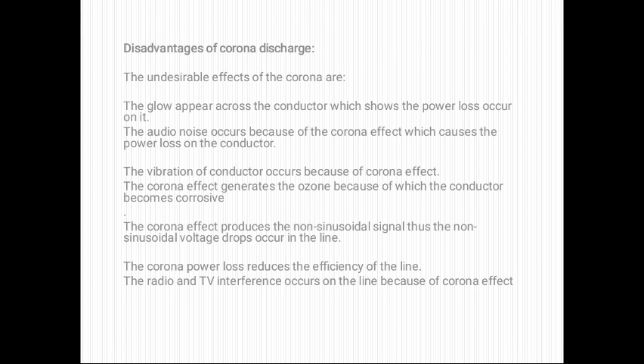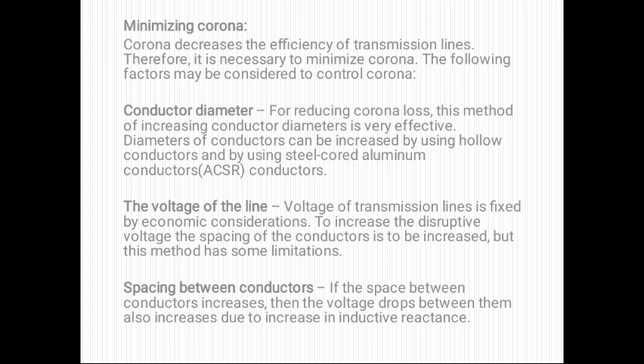Now, disadvantages of corona. Undesirable effects of corona are: a glow appears across the conductor, due to which power loss occurs in the line. Audio noise occurs because of corona effect, which causes power loss on the conductor. Vibration of the conductor occurs because of corona loss. The corona effect generates ozone, because of which the conductor becomes corroded. Corona effect produces non-sinusoidal signals known as harmonics, which cause interference in TV and radio signals. Method of minimization: we can minimize the corona effect by increasing the diameter of the conductor, by reducing the voltage of the line, and by increasing the spacing between the conductors.